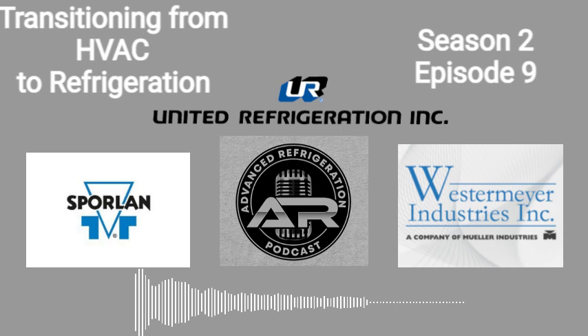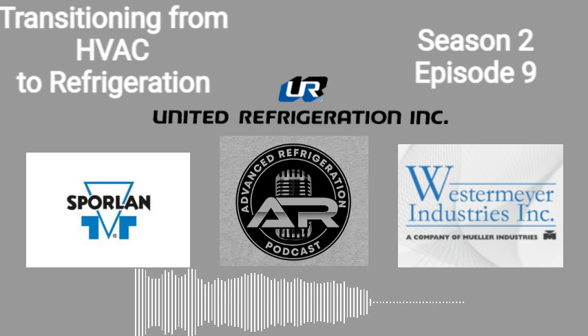For sure. Have you started doing anything different? When I'm talking to someone that does refrigeration versus HVAC, I notice HVAC guys automatically say, if you run an R22 at 100 degrees, it should be 60, 65 pounds. And if you're running 410A, it should be about a buck ten, buck twenty, somewhere in there. Where if you're talking to a refrigeration guy, everything is always saturated. The reason we do that is because there are 20 different refrigerants out there, so you're never going to remember every single PT chart out there. Yeah, exactly.